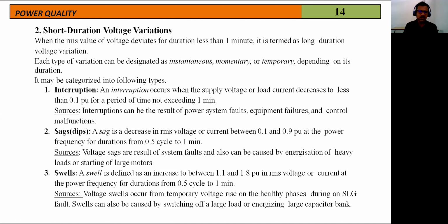Coming to the third one, swells. A swell is defined as an increase to between 1.1 and 1.8 per unit in the RMS voltage or current at the power frequency for a duration from 0.5 cycle to 1 minute. Generally, it is the same time period, either sag or swell. It ranges from 0.5 cycles to 1 minute maximum, because the short duration time period itself is less than 1 minute. But swell means it is not a decrease in the voltage or current, but instead an increase in the voltage or current.